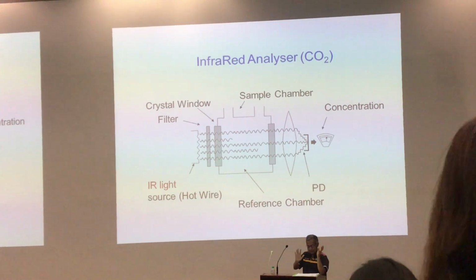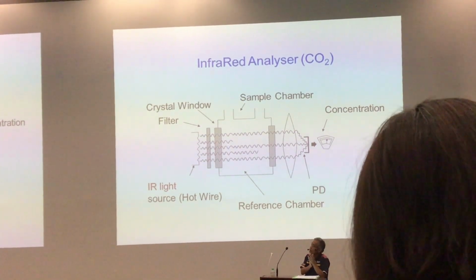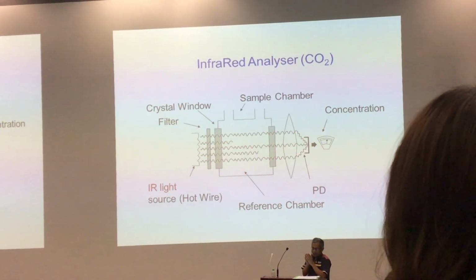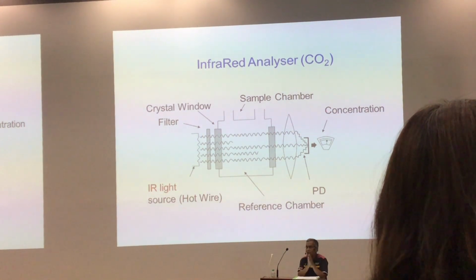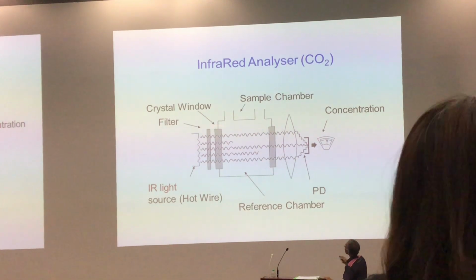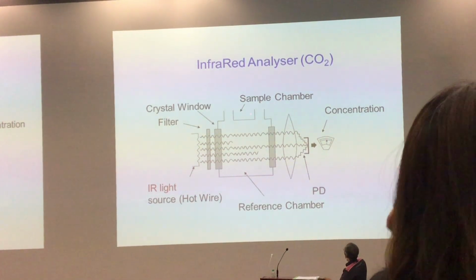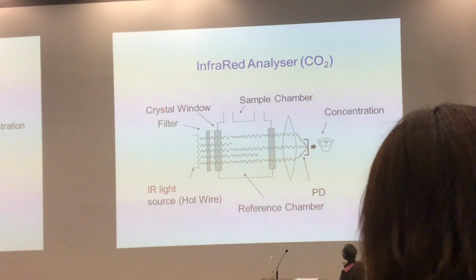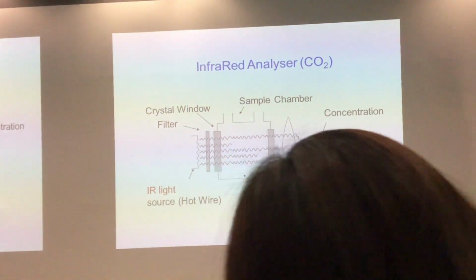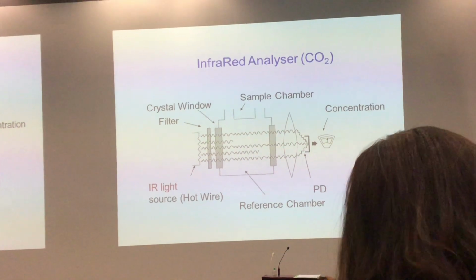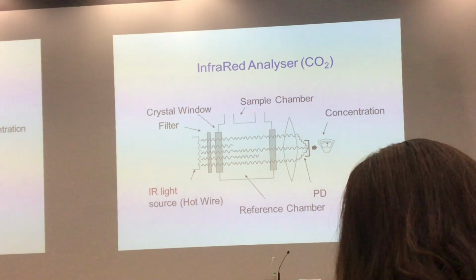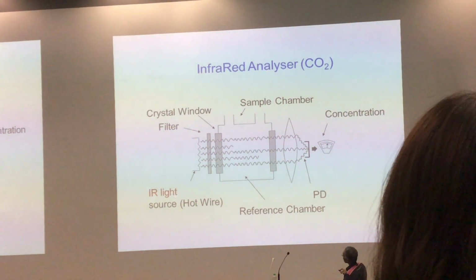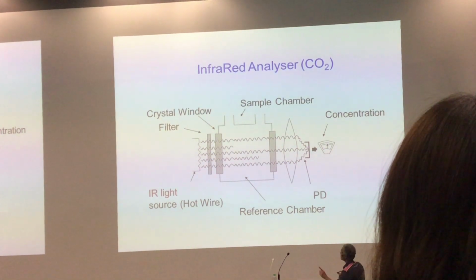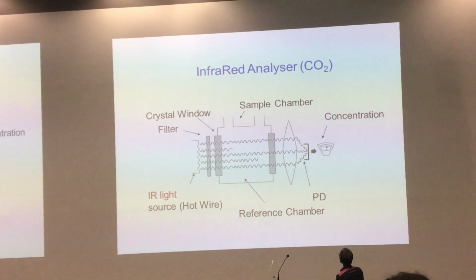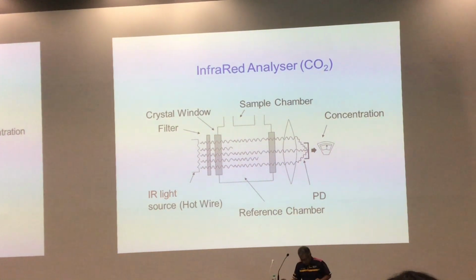This is important. The capnogram, basically, you measure the entire CO2 by using an infrared analyzer, right? Which means this is your gas sample, the sample goes in here. Your expired gas goes this way into this chamber, right? This is the reference chamber, this one is the sample chamber. You inject your expired gas. CO2 will absorb infrared. This infrared comes from a light source, a hot wire, with a certain frequency. So CO2 will absorb this certain frequency of infrared, resulting in reduced intensity of the infrared, which is detected here. So the amount of CO2 can be calculated lah.